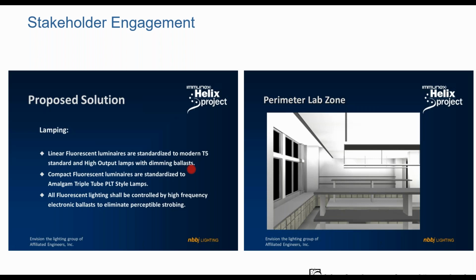There were a handful of places where we had switching ballasts rather than dimming ballasts, but for the most part, in the offices, in the labs, in some of the corridors, most of the spaces were allowed to have dimming systems. And this goes back to the early 2000s with fluorescence. So it was not inexpensive, but the end users understood how important that was for them.